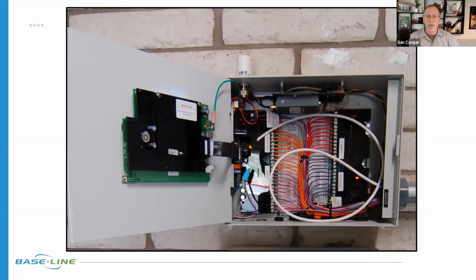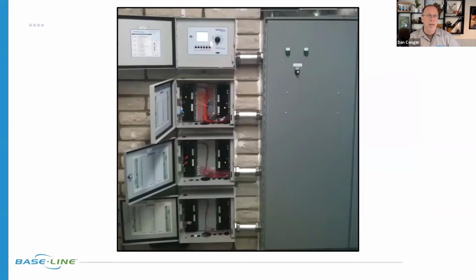So this is what he did: he set the controller at the top panel, and then he has three other cabinets, X cabinets, with 48 zones of conventional wire boards in each one. So now he has 190-some odd zones of conventional wire he can run, nearly utilizing all 200 zones, the 200-zone capability of the base station 3200.